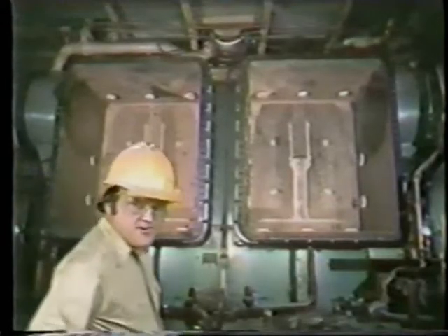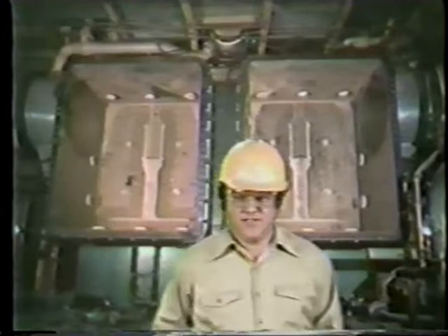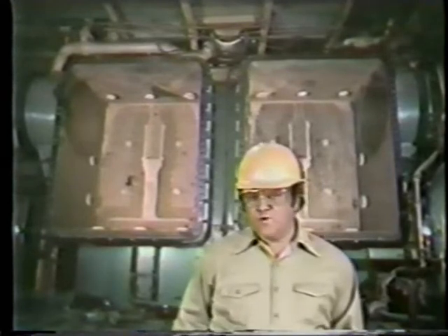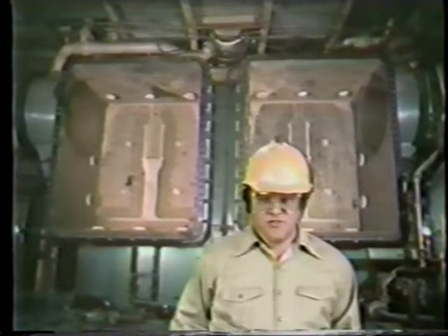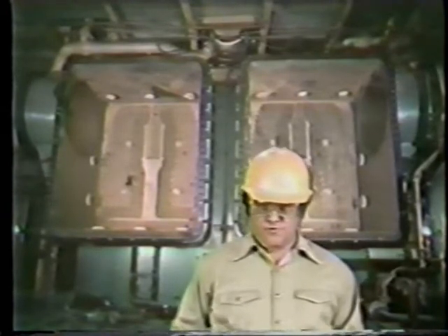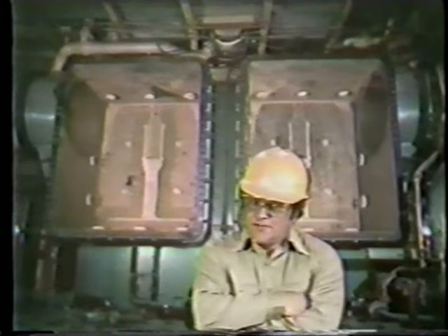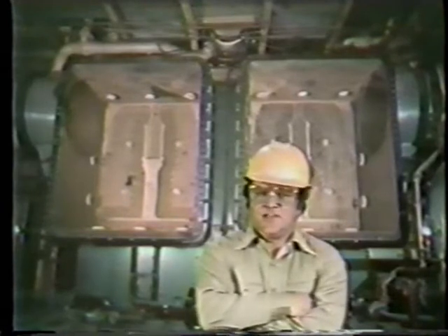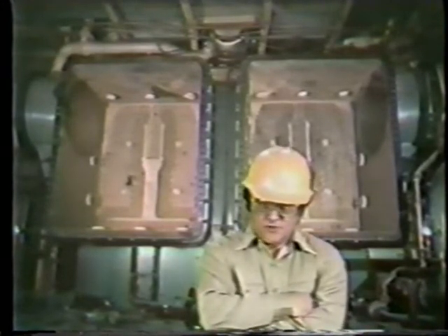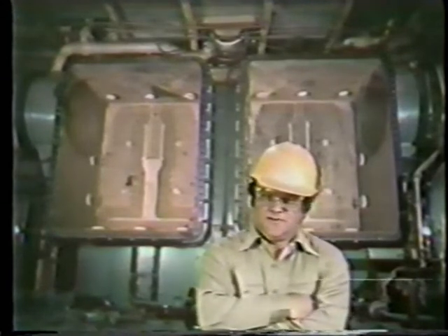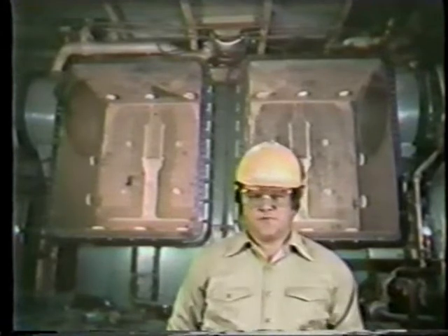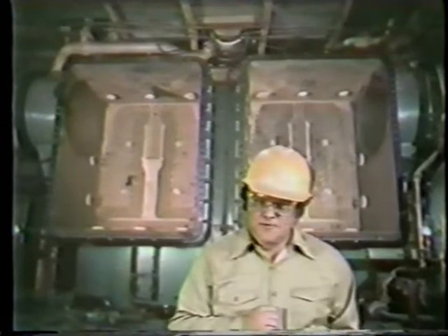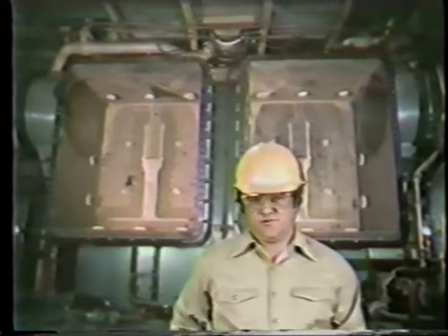It is a very common design for modern main condensers because it has considerable flexibility while in operation. For example, if a leak occurs in one of the thousands of tubes, only 1/2 of the condenser needs to be shut down. To do this, we stop the circulating water flow through the tubes of the affected half. With only 1/2 of the condenser shut down, the circulating water flowing through the other half of the condenser can continue condensing steam exhausted from the turbine. This allows the turbine to continue to operate while the leak is located and repaired. Depending on the operating conditions, the turbine load may have to be reduced while 1/2 of the condenser is out of service, but the important thing to remember is that the turbine continues to operate under these circumstances.